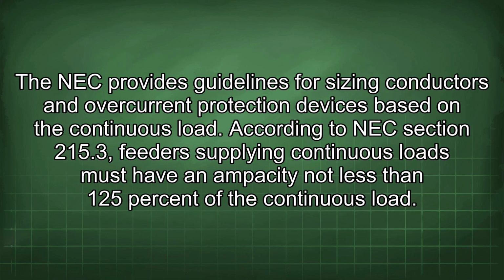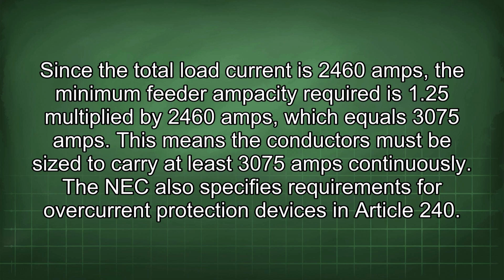The NEC provides guidelines for sizing conductors and overcurrent protection devices based on the continuous load. According to NEC Section 215.3, feeders supplying continuous loads must have an ampacity not less than 125% of the continuous load. Since the total load current is 2460 amps, the minimum feeder ampacity required is 1.25 multiplied by 2460 amps, which equals 3075 amps. This means the conductors must be sized to carry at least 3075 amps continuously.